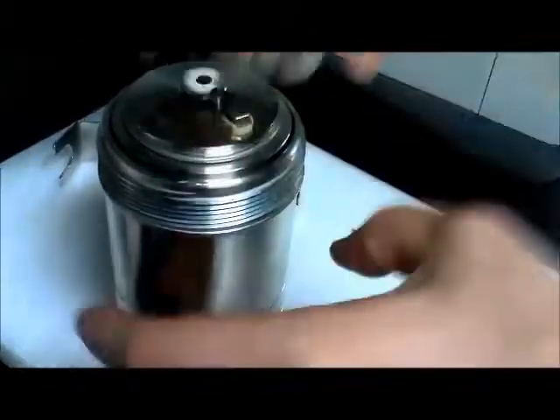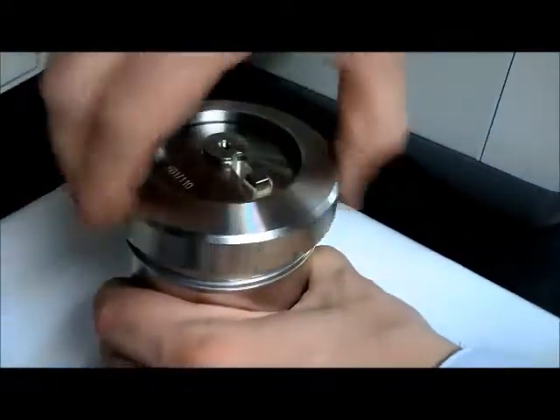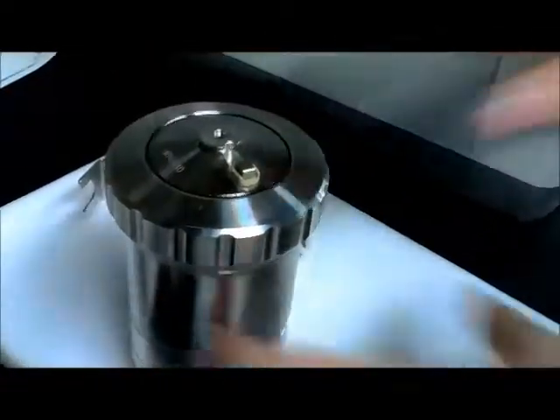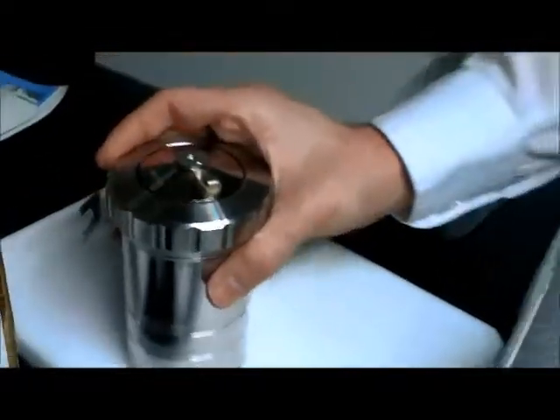That doesn't twist, and you're just pressing that. You press that in, and you have to be careful so you don't shift your materials inside. Right. Use the lock union nut. Twist it only to hand tight, don't use any kind of machine. Hand tight. And then you are ready to fill the bomb with oxygen. Okay. So we're going to take it over to the filling station. That's the fun part.